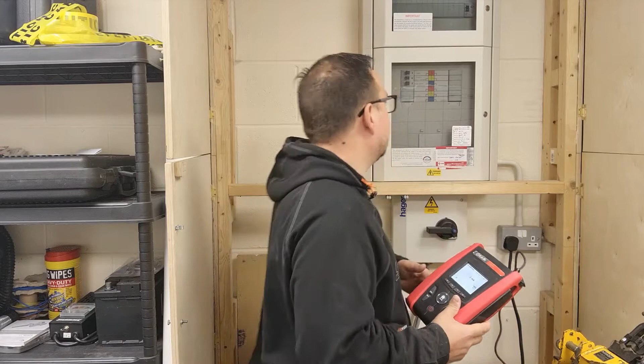So if we remove the clamp now, and you can see I've gone into the leakage measurement clamp, and if we pop it around all of the conductors, so this is this 3-phase board, and we've got a couple of socket circuits and the lighting circuits. Obviously the lights are all on, and we're measuring 2 milliamps there of leakage current, and if we adjust that actually to 50 amps on there, and 100, so you can change the scale as well.